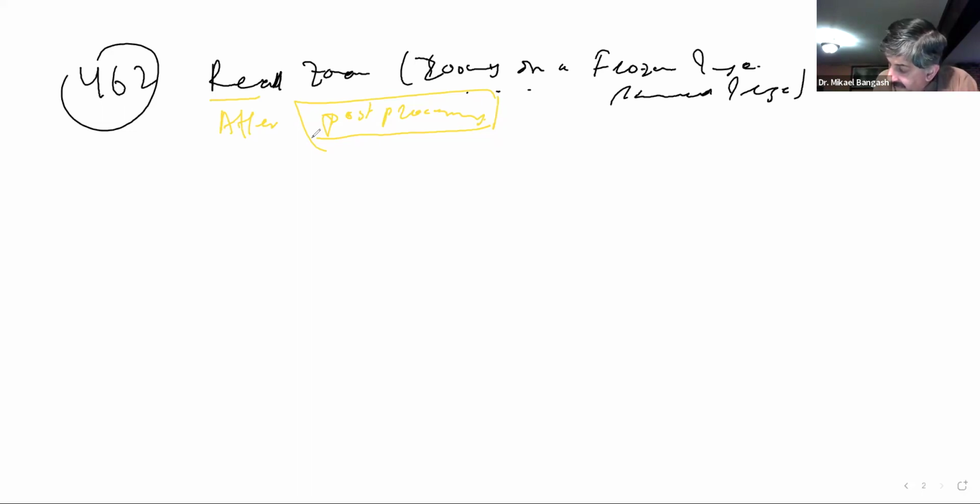The same number of ultrasound pulses are used to create the original image or original region of interest and the zoom in image. Yes. Option C is wrong.